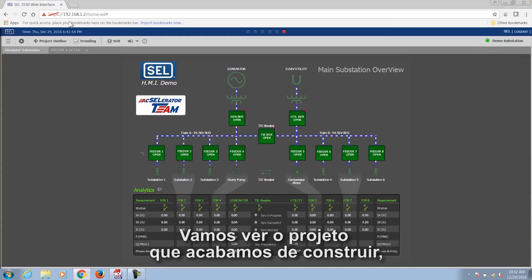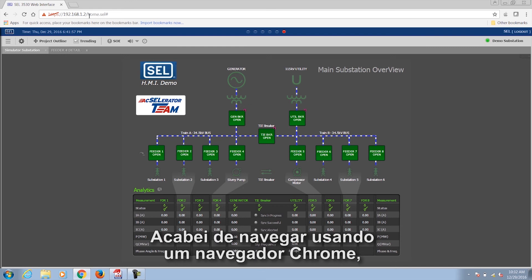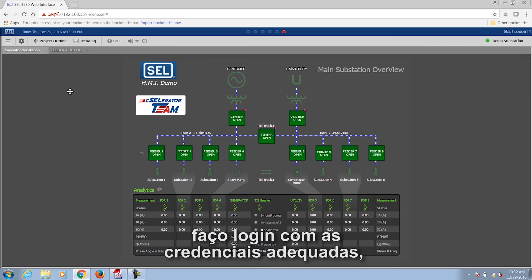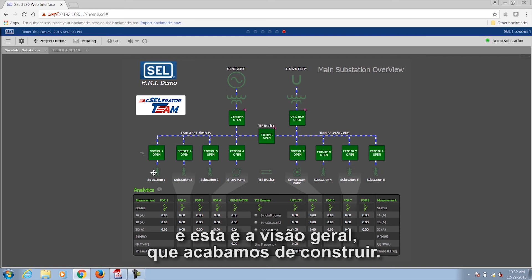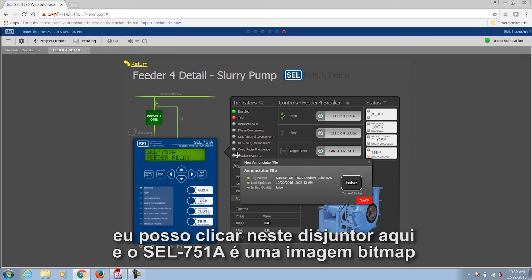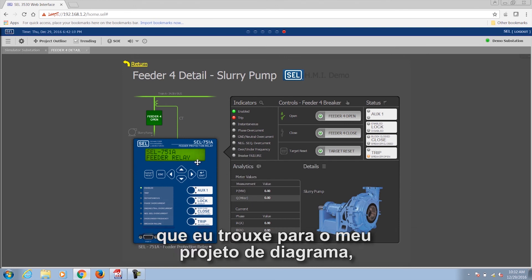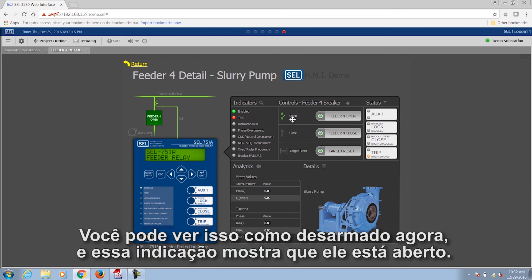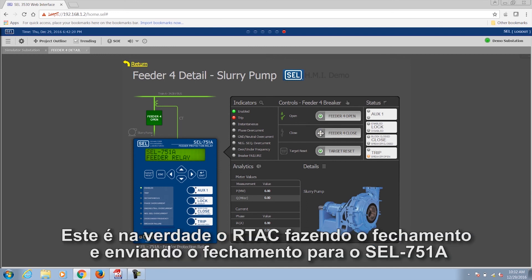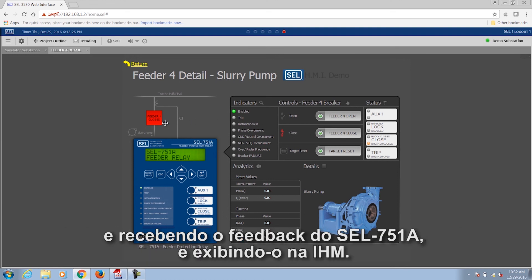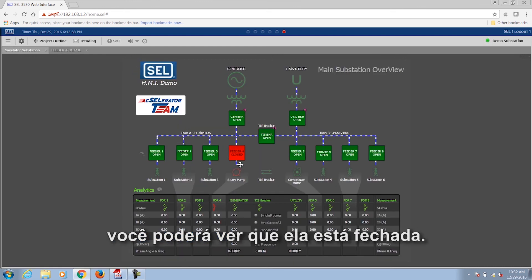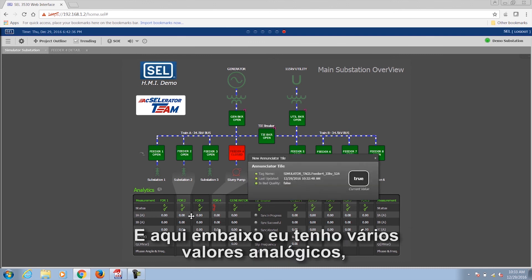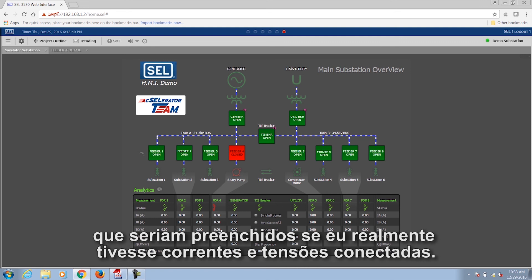Let's view the project we just built — this is the RTAC web interface. I navigate using a Chrome browser, log in with proper credentials, and this is the overview we just built. I can send controls — I can click on this Breaker here, and the 751A is a bitmap image I brought into my diagram project. I can do controls to it; you can see it is tripped right now and this indication shows it's open. I click Close, and the RTAC does the closing and sends the close command to the 751A, receives feedback from the 751A, and displays it on the HMI. You can see that it is now closed. Down here I have analog values that will be populated if I had actual currents and voltages connected.